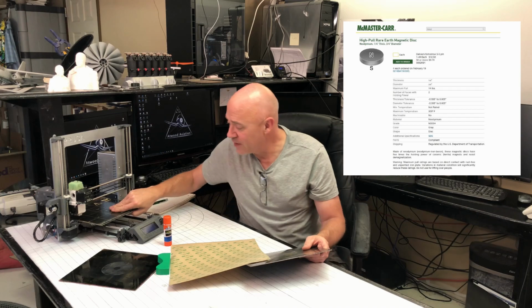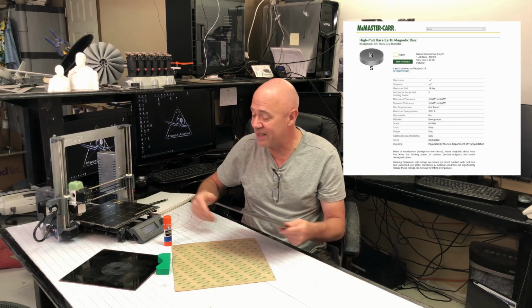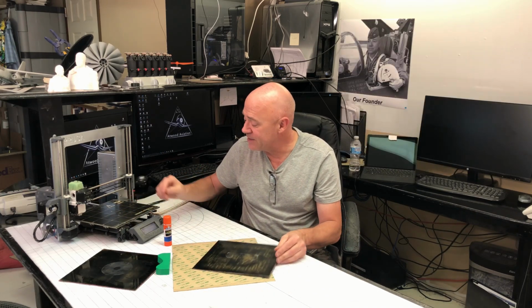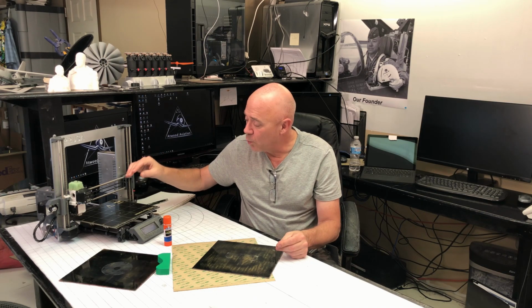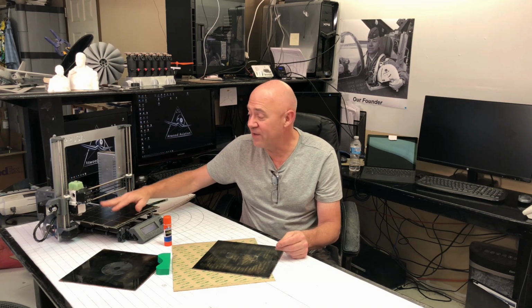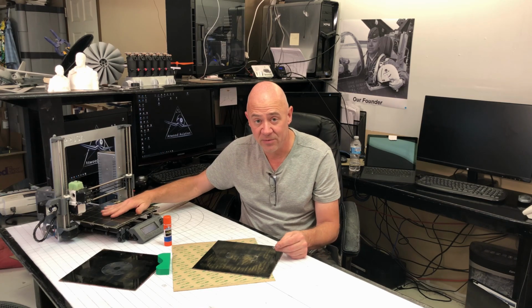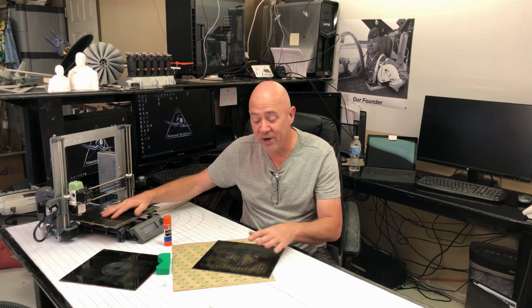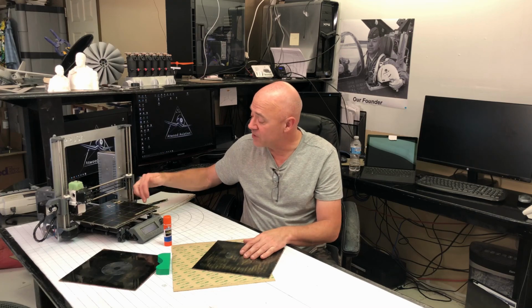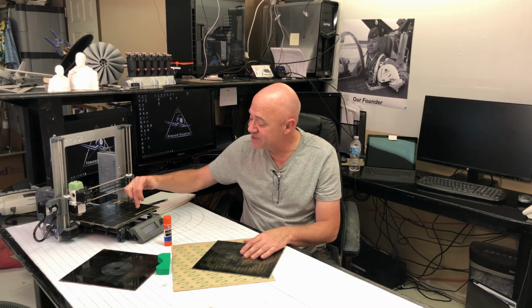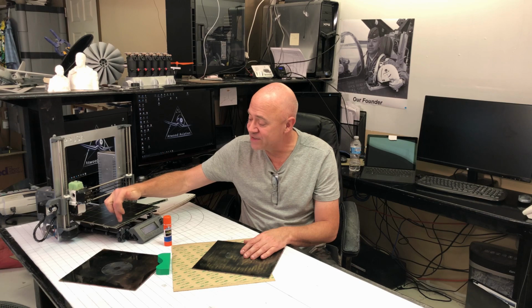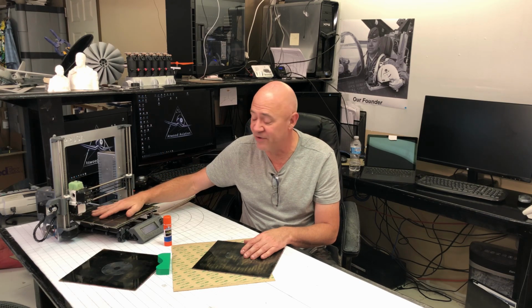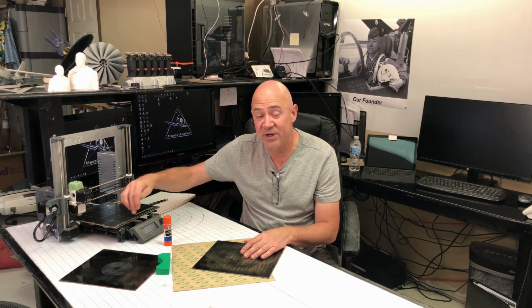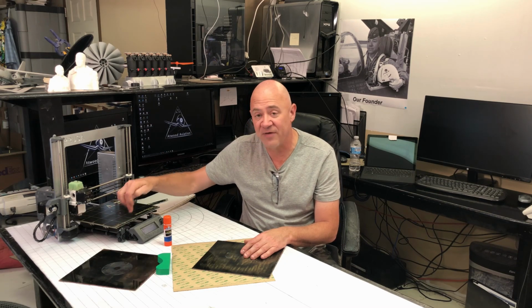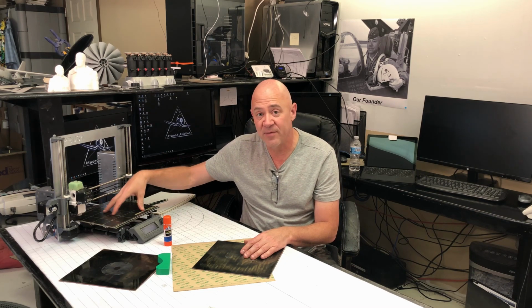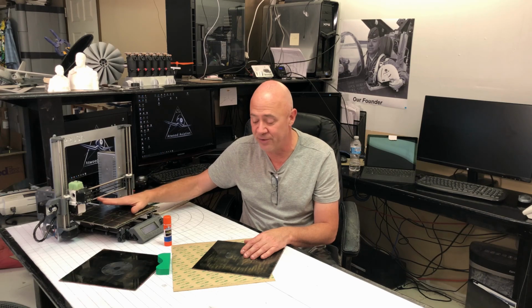Now, one thing I want to explain that a lot of people have asked me about is, will the metal affect the way that the machine runs? And the answer is no. However, when you calibrate, you can't have the metal on the bed, because when it calibrates, it's looking for very specific metal points that are embedded in it, I believe. I think that's how they're doing it. So as it does a calibration for the X, Y, and Z, it's going to take about 5 minutes to go through all these different points, calibrate the machine, and say it's good.